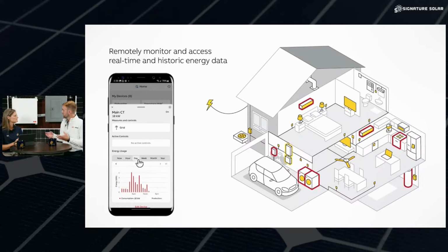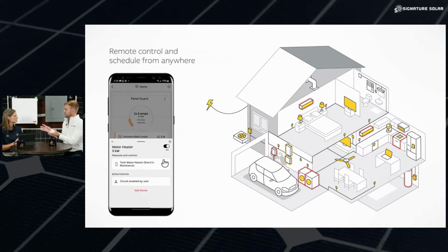From a physical perspective, we're simply mounting this hardware, the smart panel itself, somewhere in close proximity of the distribution panel or load center you want to control breakers in. From there, there may be other variables we're monitoring, like your service lines for whole home consumption. It comes with a set of 200 amp CTs, and we may add an additional optional set of CTs for your solar or generation sources.